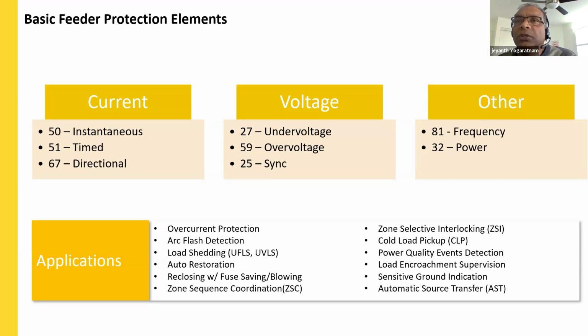And the feeder relays can be used to fulfill certain specific applications, which are commonly found in the industrial and utility environment. The feeder protection relay can simply be used for overcurrent protection for radial feeders or mesh feeders or ring feeders. It can provide overcurrent protection, as well as arc flash detection, load shedding, under frequency load shedding, under voltage load shedding, and it can also perform auto reclosing, zone sequence coordination, reclosing with fuse saving and fuse blowing, zone selective interlocking, cold load pickup, etc. There are certain dedicated functions the feeder relay can be used for, in addition to the protection elements, to fulfill certain application requirements.